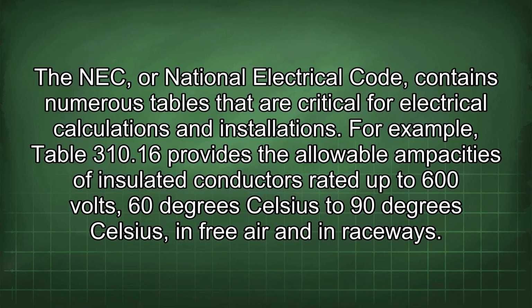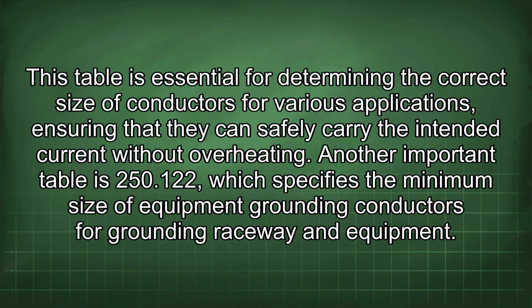The NEC, or National Electrical Code, contains numerous tables that are critical for electrical calculations and installations. For example, Table 310.16 provides the allowable ampacities of insulated conductors rated up to 600 volts, 60 degrees Celsius to 90 degrees Celsius, in free air and in raceways. This table is essential for determining the correct size of conductors for various applications, ensuring that they can safely carry the intended current without overheating.